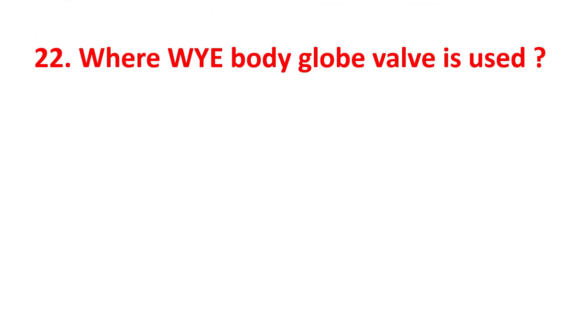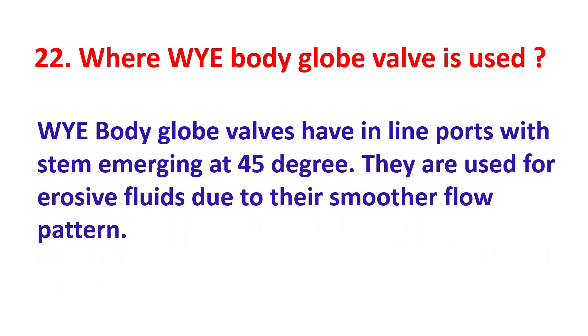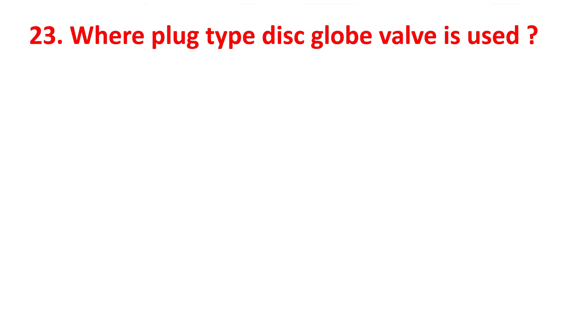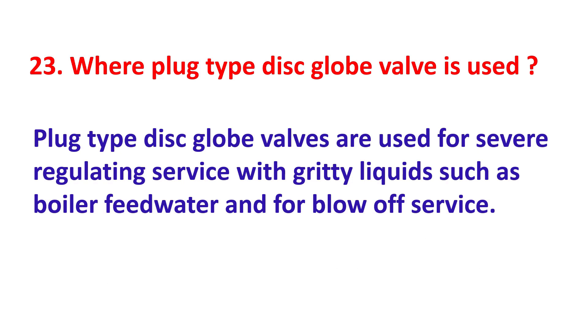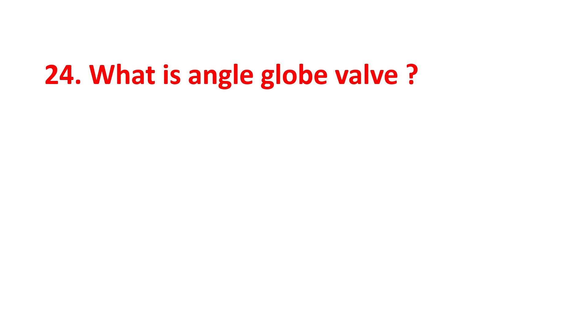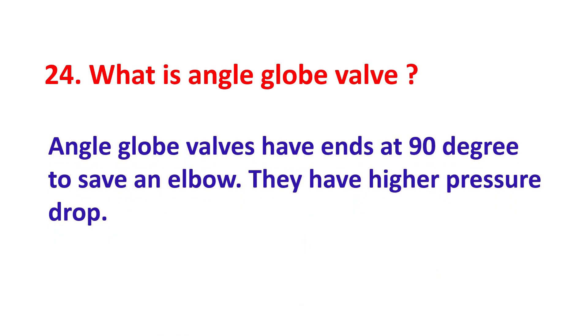Where is the WYE body globe valve used? WYE body globe valves have inline ports with the stem angled at 45 degrees. They are used for erosive fluids due to their smoother flow pattern. Where is a plug type disc globe valve used? Plug type disc globe valves are used for severe regulating service with gritty liquids such as boiler feed water and for blow-off service. What is an angle globe valve? Angle globe valves have ends at 90 degrees to save an elbow and have higher pressure drop.